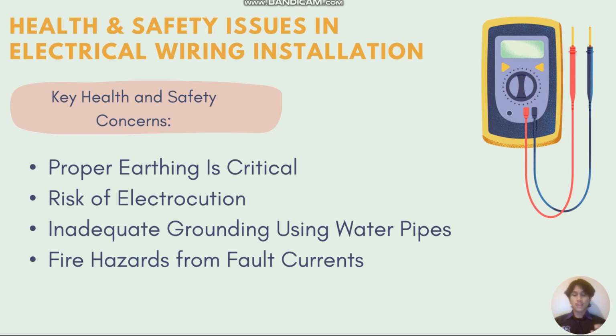For example, pipes can corrode or be replaced with non-conductive materials, which is PVC. Water pipes carry water, which is a conductor, but may not provide consistent grounding, especially in wet environments like a restaurant, increasing shock and fire hazard. And the fourth point is fire hazards from fault currents.